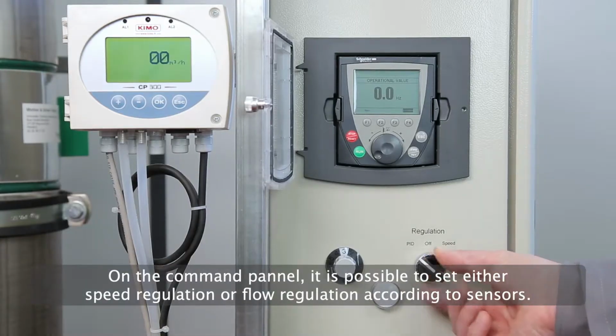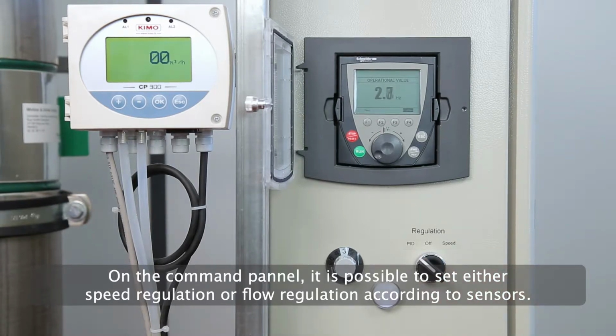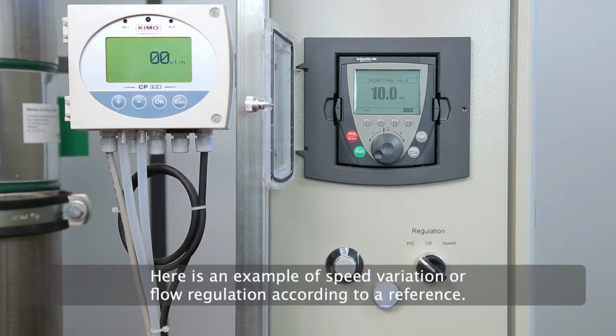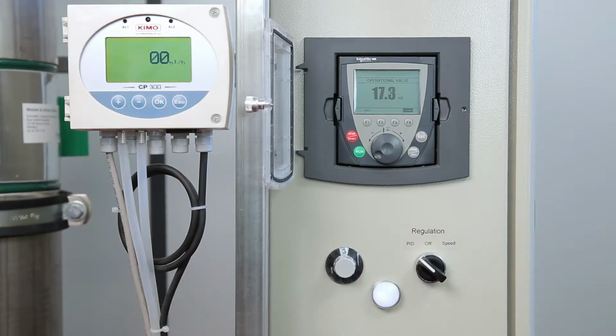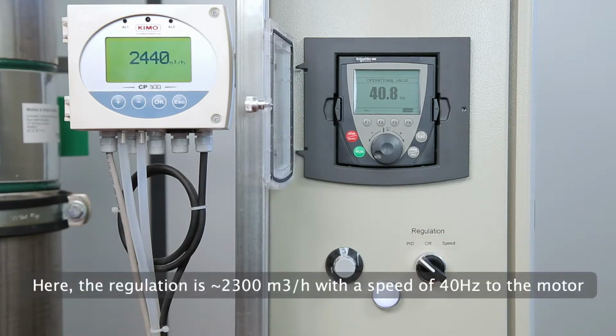On the command panel, it is possible to set either speed regulation or flow regulation according to sensors. Here is an example of speed regulation or flow regulation according to a reference. Here, the regulation is around 2,300 cubic meters per hour with a speed of 40 Hertz to the motor.